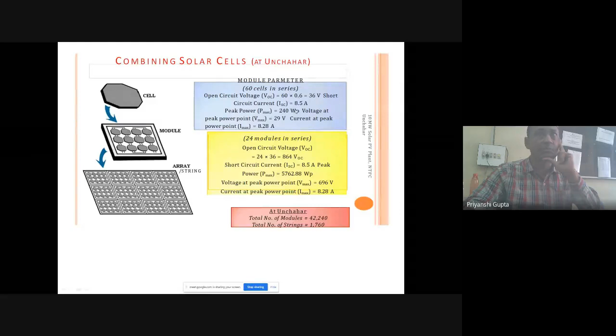This is the open circuit voltage: insolation falls on the panel, you don't connect any load, open both terminals, and measure the voltage. Now you short both terminals, and the current that flows is called the short circuit current. This represents the maximum power it can produce. Based on these parameters, we decide whether the panel needs to be changed or we can continue with it.